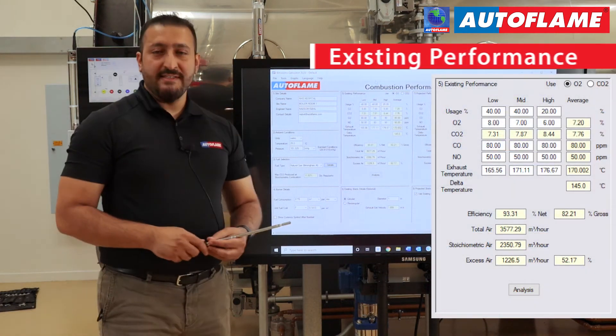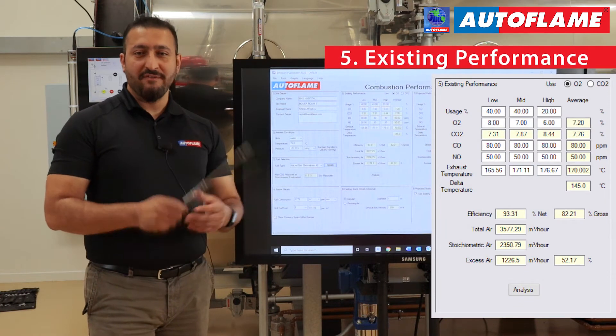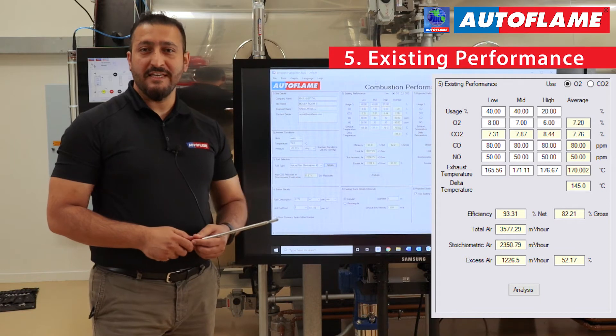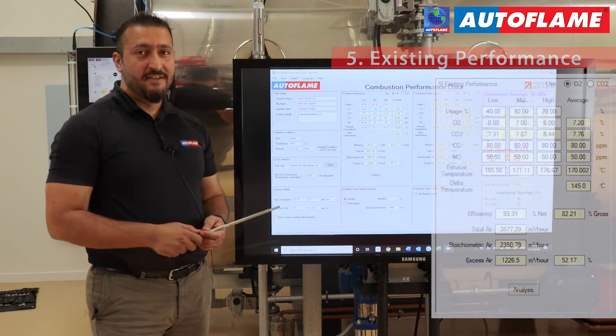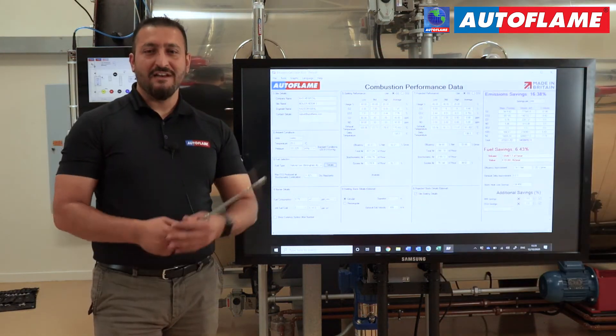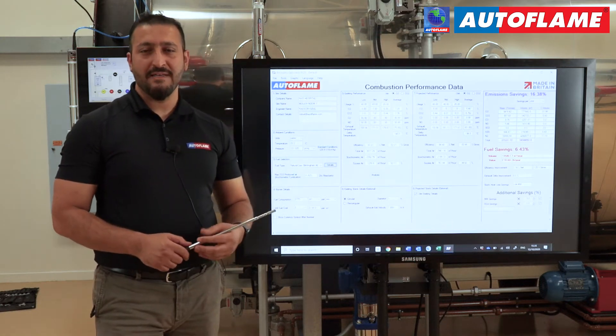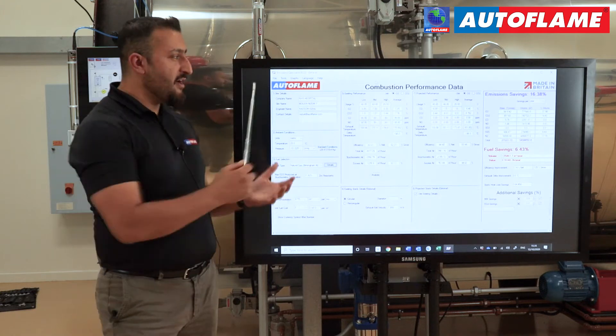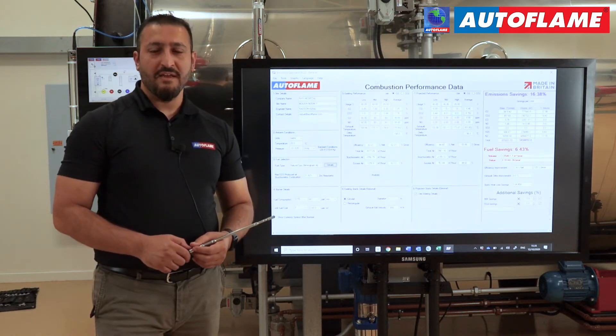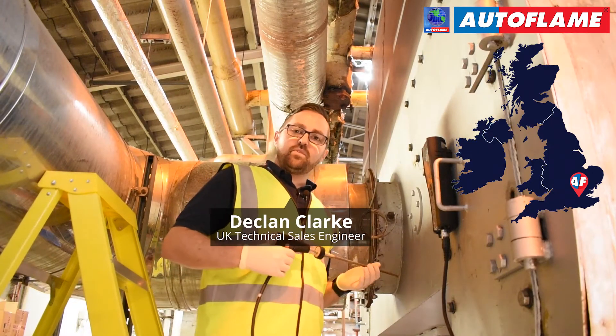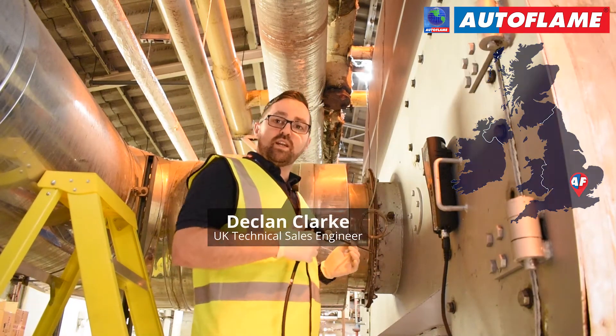Section five is your existing performance. This is where I will ask my friend Declan to pass on the information for a combustion audit he's just carried out at the NHS site. Declan, if you can kindly send me the information on CO, O2, stack temperatures for the NHS site, then I can proceed further with the emissions calculator. The boiler runs off natural gas. I'm going to take some readings now from the test point in the rear stack.